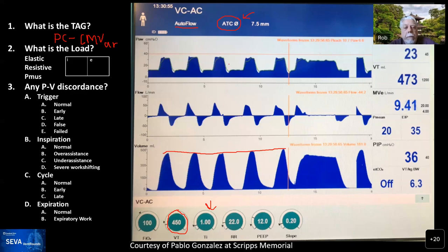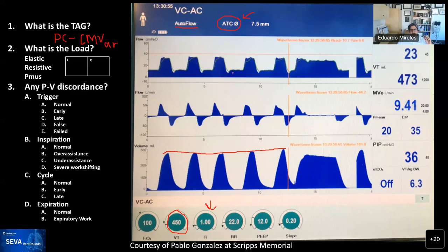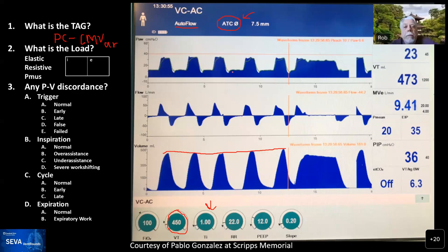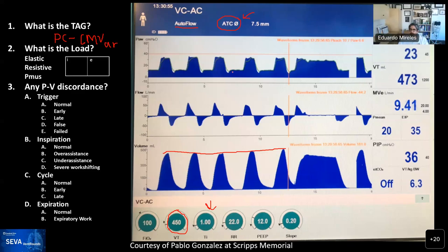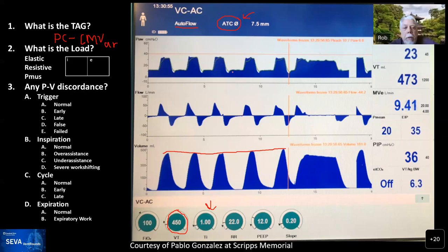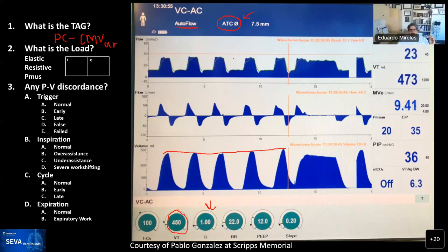Rob: For whatever reason, ventilator manufacturers have allowed you to add ATC on top of mandatory breaths or pressure control breaths. It was originally designed for use in CPAP. Adding it on top of breaths already supporting both elastic and resistive loads — I have no idea why you would do it. That just confuses the weaning process. There's no logical explanation I've ever seen for why you'd do that in this situation.